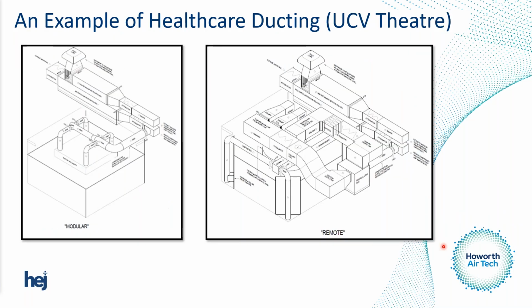So keeping in mind the 10 times the diameter of the ducts and making sure that the air is laminar to make an adequate traverse and calculation of an air change rate or a total volume of an air handling unit. Probably the most complex arrangement that we'll get in a UCV operating theatre is the UCV. The ductwork configuration can at times be significantly different to a conventional operating theatre or a recovery suite or whatever it might be. And the reason is this.